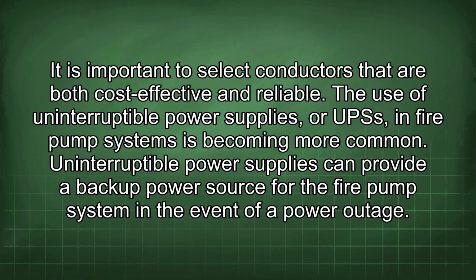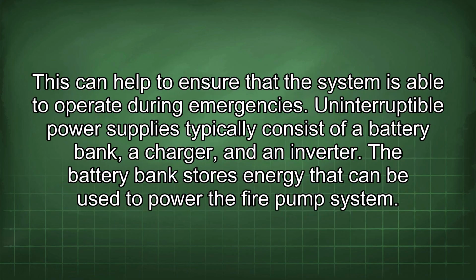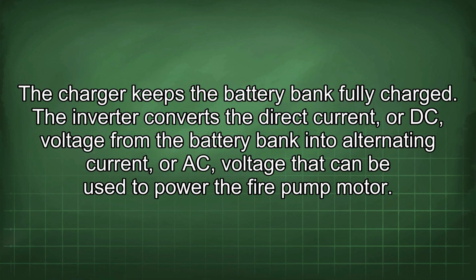The use of uninterruptible power supplies, or UPSs, in fire pump systems is becoming more common. Uninterruptible power supplies can provide a backup power source for the fire pump system in the event of a power outage. This can help to ensure that the system is able to operate during emergencies. Uninterruptible power supplies typically consist of a battery bank, a charger, and an inverter. The battery bank stores energy that can be used to power the fire pump system. The charger keeps the battery bank fully charged. The inverter converts the direct current, or DC voltage, from the battery bank into alternating current, or AC voltage, that can be used to power the fire pump motor.